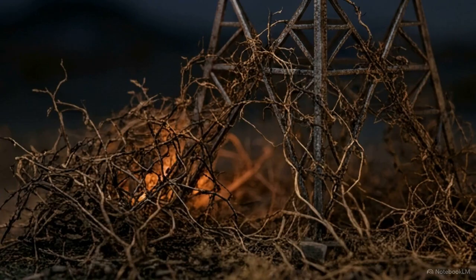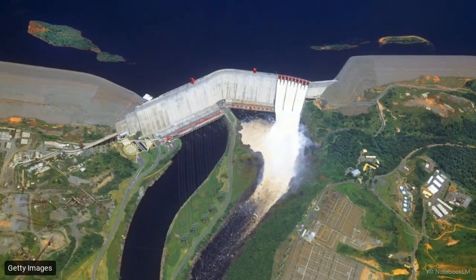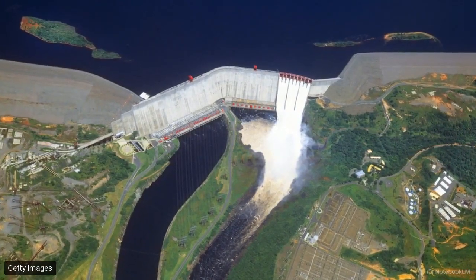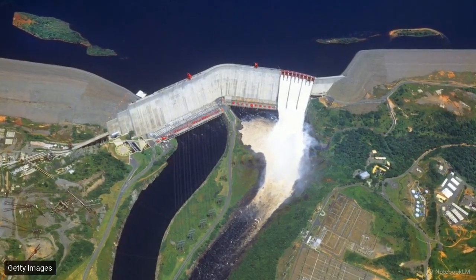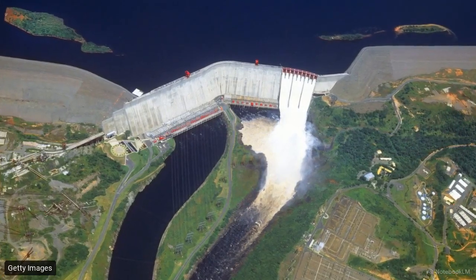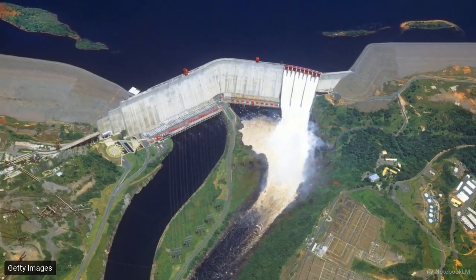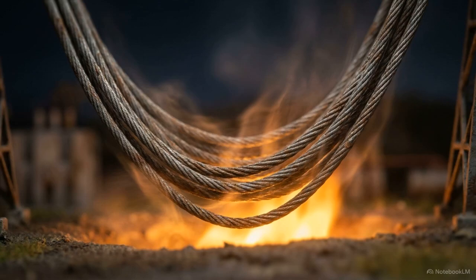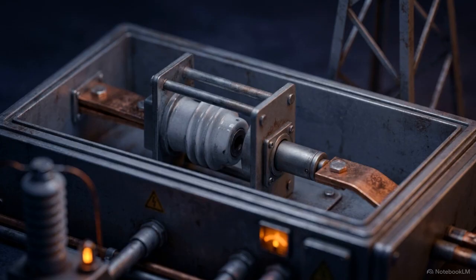The 2019 Venezuela blackout was triggered by months of neglected brush pruning near the nation's most critical transmission corridor. During a dry season, that vegetation caught fire directly under the 765 kilovolt lines that transport 80% of the country's power away from the Guri Dam. As the lines overheated and sagged toward the fire, automated protection relays detected the fault and instantly disconnected the lines to prevent the physical cables from melting.